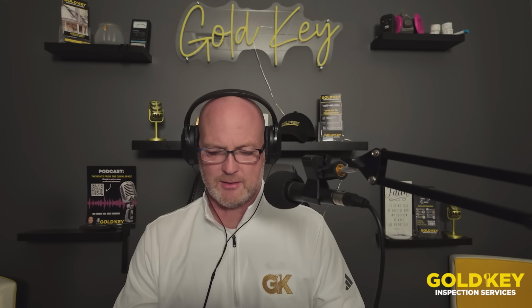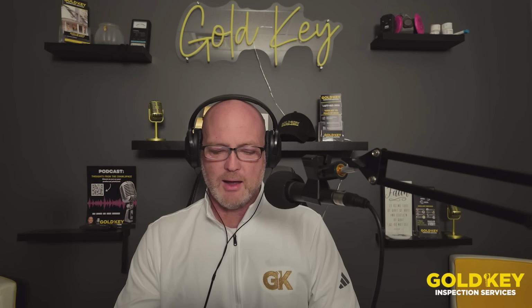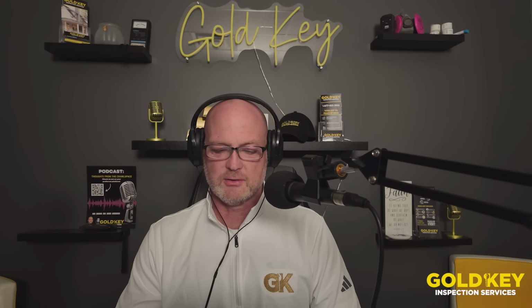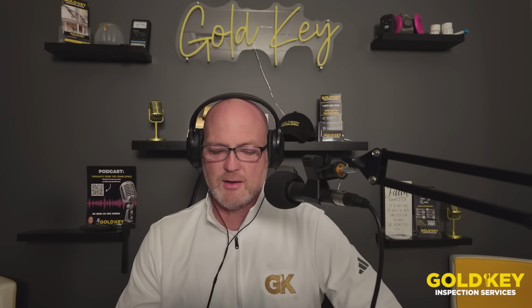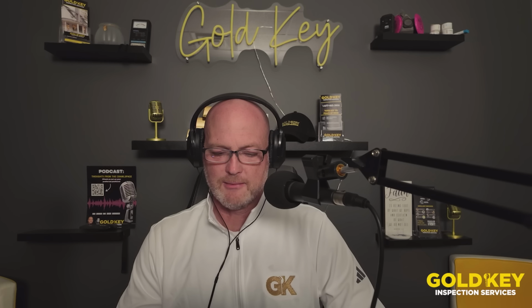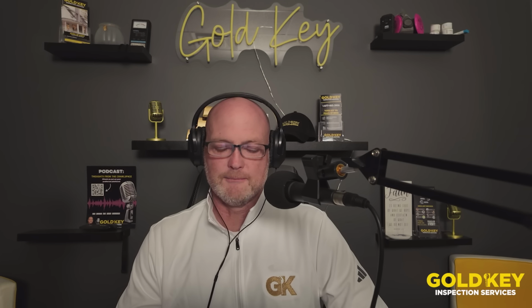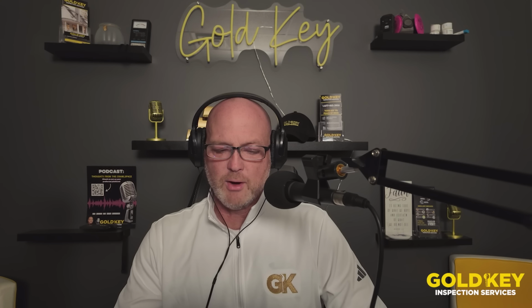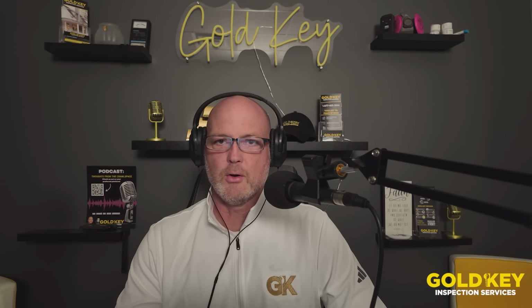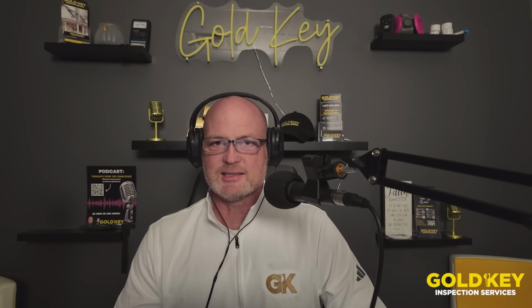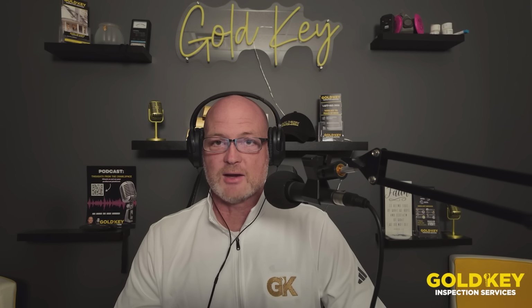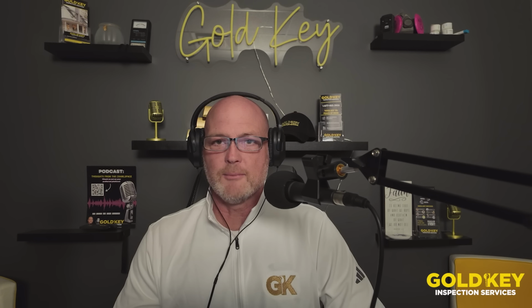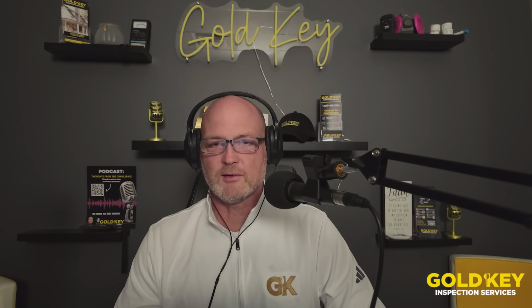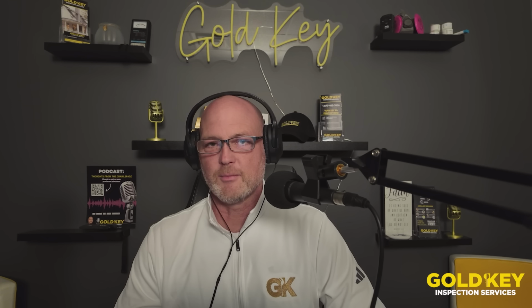So what does a home inspector check? Well, number one thing I check on a home inspection on the air conditioner is the data plate. The data plate is going to give you the age, the model, and the capacity. Capacity means the cooling ability. The age is always located in the serial number, or it has a specific space that says this AC was manufactured at blank. With the serial number, you have to have a little bit of experience to know where to look, but generally it's going to be in the first two or the second two numbers in the serial number. Sometimes it's at the very end of the serial number.